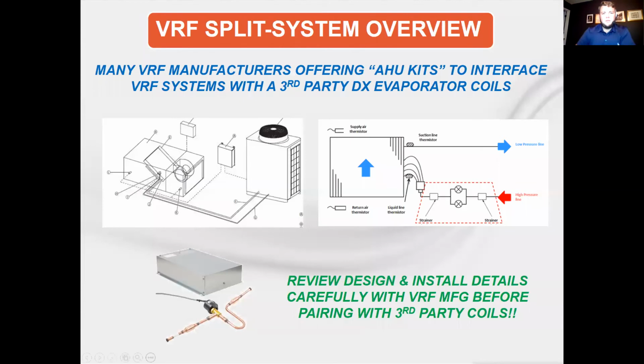So the other portion that we're bringing up during this presentation is new technology, which is pairing the VRF systems with third-party air handler or evaporator coils in general in that application. It parallels a lot with our DX discussion in the sense that they're the same type of generic design, where you have an outdoor condensing unit with the same components out there, and then you pair that with an indoor unit that also contains an evaporator coil and expansion valve. So it's the same idea, and I'll follow up on the benefits after this, but for now I just want to do a little overview of how that compares with the traditional DX systems.